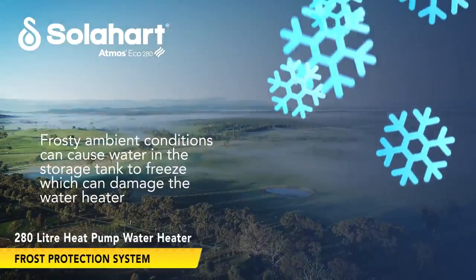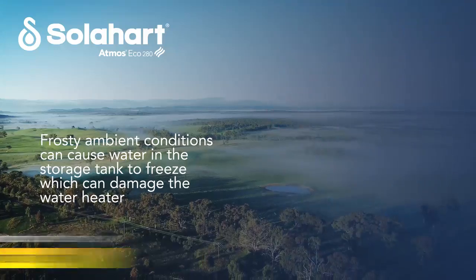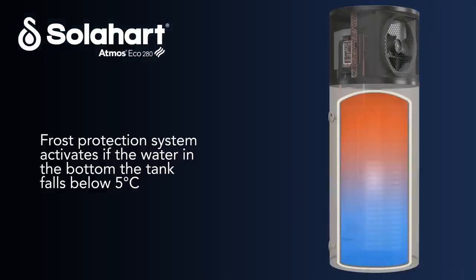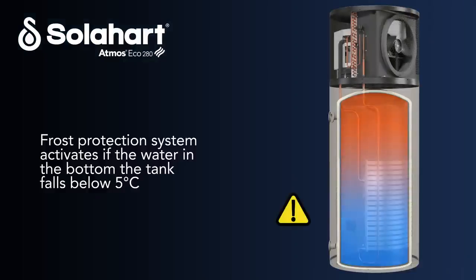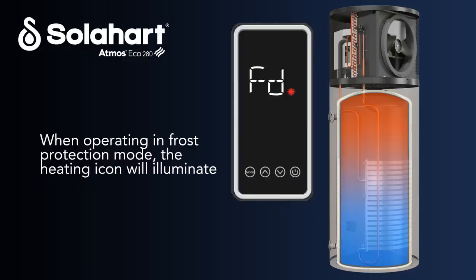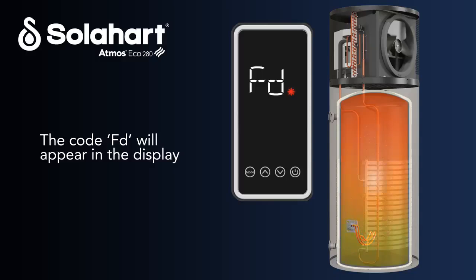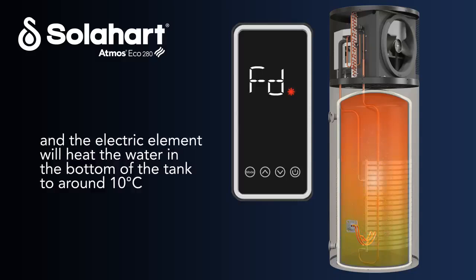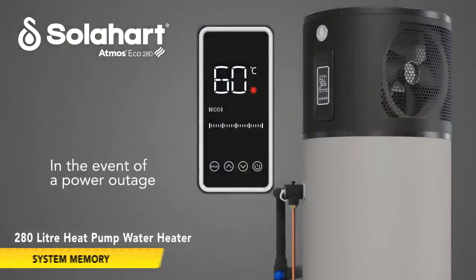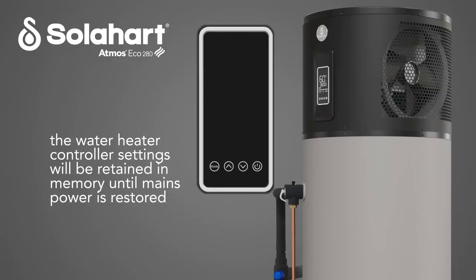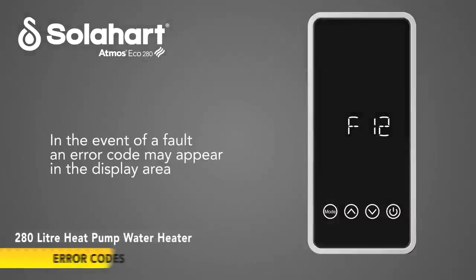Frosty ambient conditions can cause water in the storage tank to freeze, which can damage the water heater. The water heater's frost protection system activates if the water in the bottom of the tank falls below 5 degrees. When operating in frost protection mode, the heating icon will illuminate, the code FD will appear in the display, and the electric element will heat the water in the bottom of the tank to around 10 degrees. In the event of a power outage, the water heater controller settings will be retained in memory until mains power is restored.